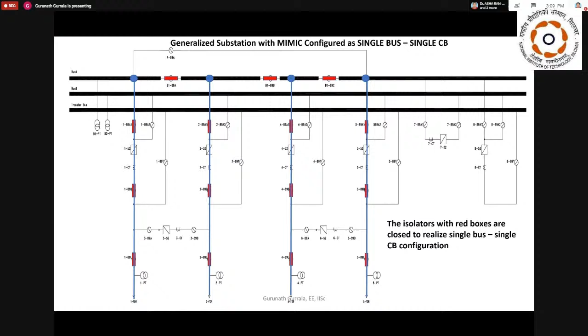So that's how we have to do the programming and stop operation of these switches. It is a big programming effort which one master student has done. It's 250 pages of PLC code that has been developed for this particular substation. So this is how I can do a single bus single CB. That means only one bus is always energized and all feeders can be served.